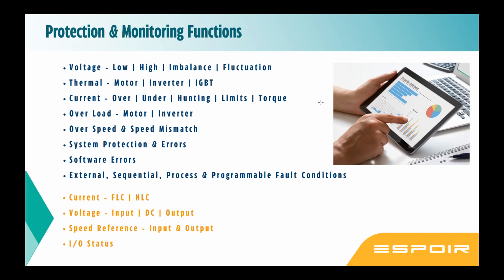Number two is a thermal trip. It trips on overheat. You need to set a thermistor for motor, inverter, IGBT overheat. All this independent heating can be sensed, and inverter overheat, IGBT overheat is sensed inside. Motor overheat, you need to give externally. And there are PT sensors available. PT interface is also available in a drive. The external PT interface you can also give directly.